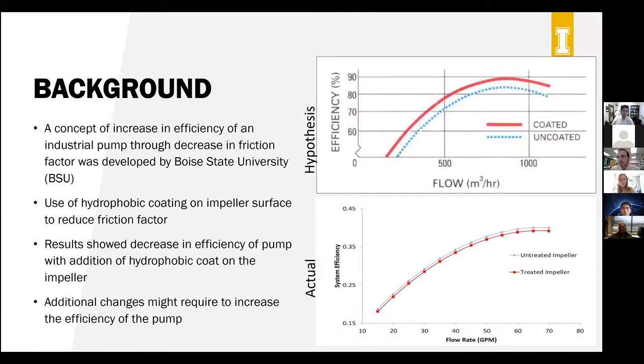So as I previously mentioned, this builds on the base that BSU initially developed. Their concept was to look at increasing pump efficiency through decreasing the friction factor of their impeller and looking at how that affects pump performance. The original hypothesis was that applying this hydrophobic coating to an impeller will increase the efficiency. And through their analysis and development, they actually showed the opposite was true. After they applied hydrophobic coating to the pump impeller, the reduction in friction actually reduced the efficiency of the pump performance, which is kind of a conundrum and left us thinking that maybe there are ways to use hydrophobic coating but still improve that pump efficiency. And so that comes primarily from the impeller redesign that we've started to present.